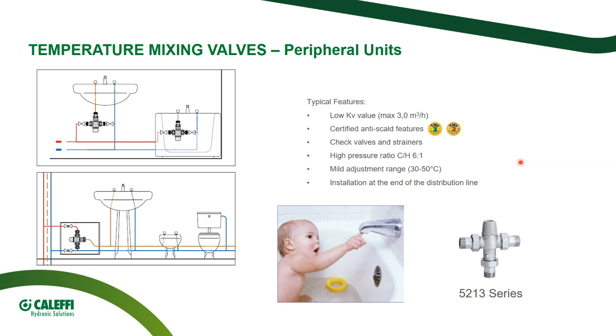They are usually equipped with built-in check valves and strainers at the inlet. They are engineered to manage a very high pressure ratio. If you remember, before, the maximum pressure ratio was 2:1. Easy, because we were in the thermal room in stable condition. In the distribution, depending on the demand, we can have very high fluctuation, and these valves are engineered to comply with a pressure ratio between hot and cold, or reverse, up to 6:1. That is a very high value.